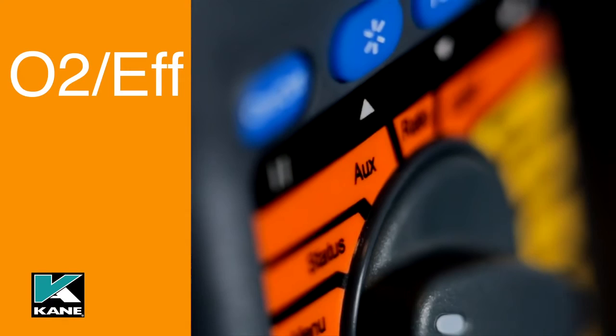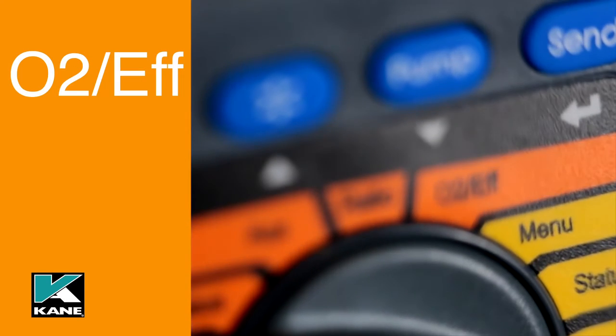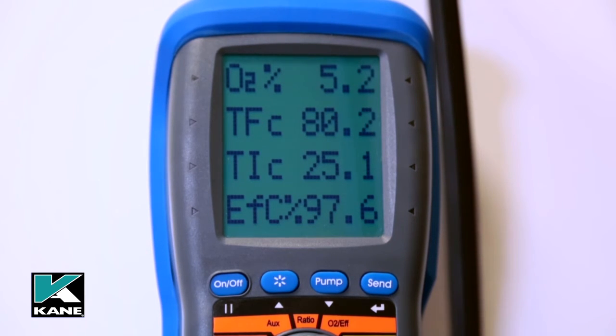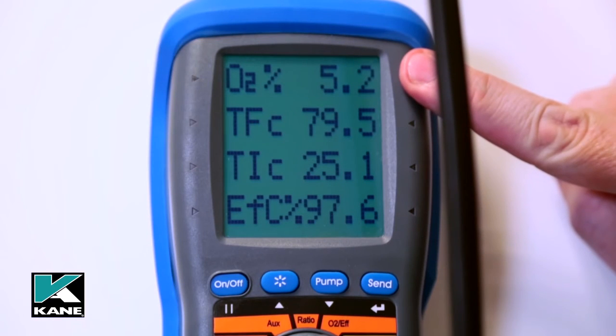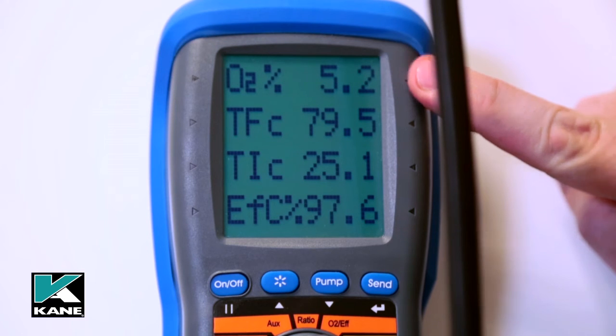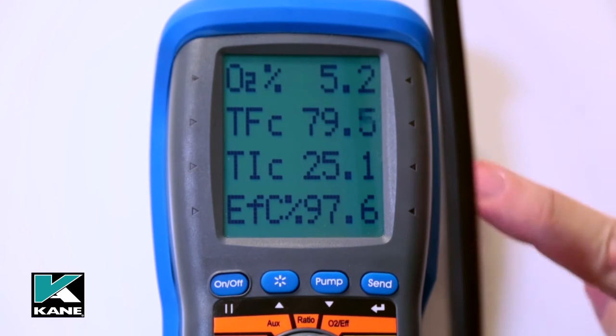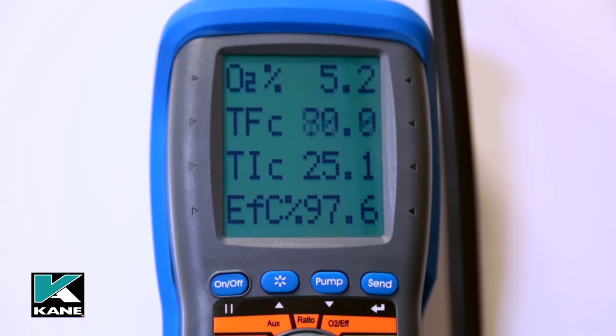Oxygen combustion efficiency, shown as O2 EFF. As part of the combustion test readings, you can also check on screen the oxygen levels, flue temperature and combustion efficiency. With the flue probe still in place, rotate the dial to oxygen combustion efficiency O2 EFF and the screen should look like this: oxygen left after combustion, flue temperature in degrees Celsius, inlet temperature (normally set by the flue probe during the fresh air purge), and condensing boiler efficiency EFC — this can be changed via menu.